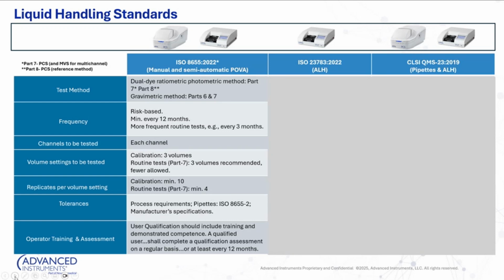Now, with regards to tolerances, I have a specific slide that we're going to talk about, but ISO provides a little bit of autonomy. They say, listen, laboratory, you can certainly define your own tolerances based on that device's process requirements, or ISO 8655 Part 2 provides some permissible error tables for some very distinct classifications of devices, air displacement pipettes, etc. Or you could use the manufacturer specifications. I'm going to talk about this in a subsequent slide, because there are some things that you should consider when you think about tolerances.